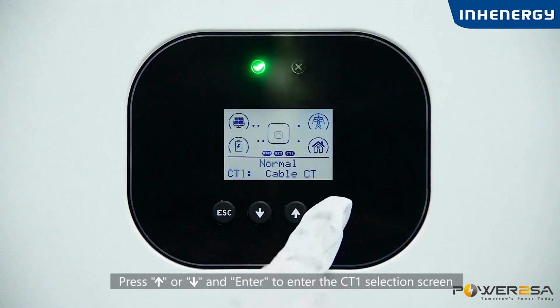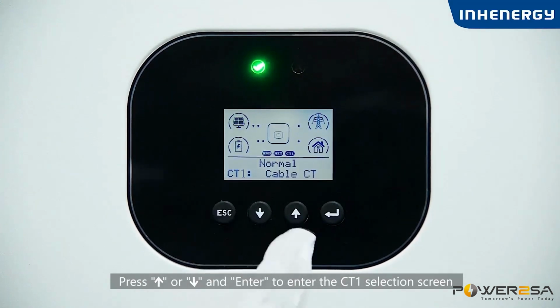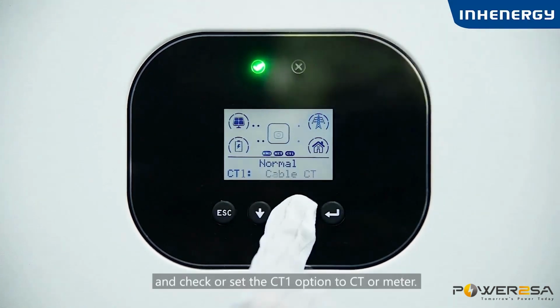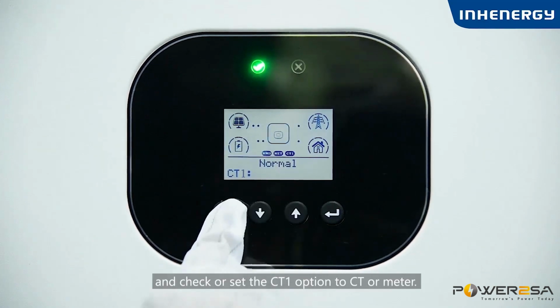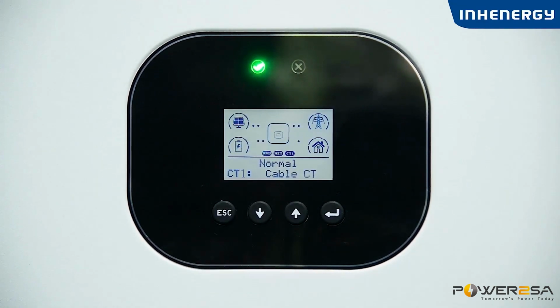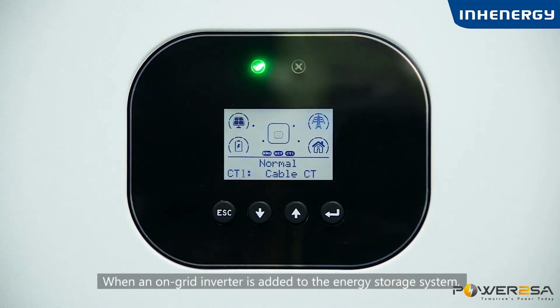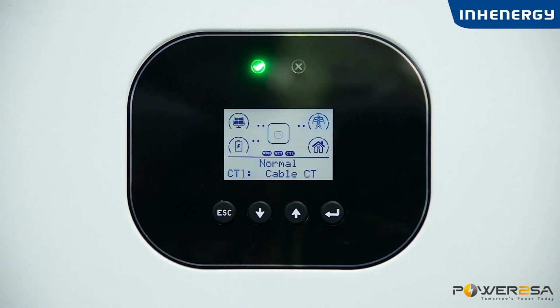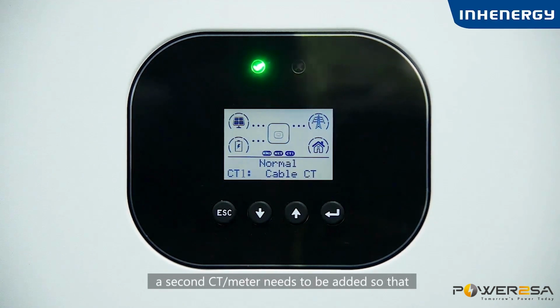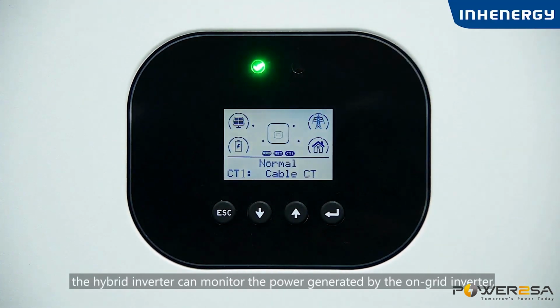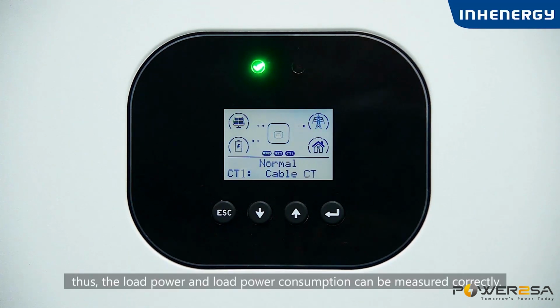Press up or down and enter to enter the CT1 selection screen and check or set the CT1 option to CT or meter. When an on-grid inverter is added to the energy storage system, a second CT or meter needs to be added so that the hybrid inverter can monitor the power generated by the on-grid inverter. Thus, the load power and the load power consumption can be measured correctly.